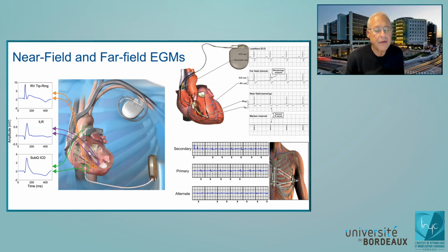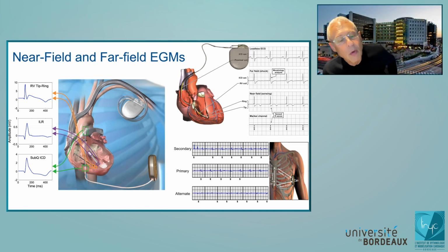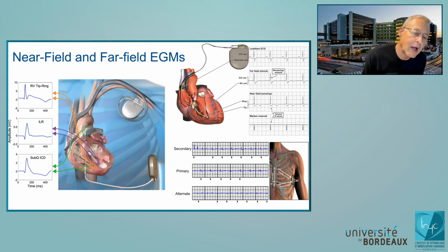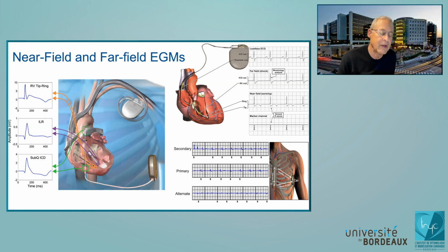The sensing characteristics of the primary sensing vector, which is between two small ring electrodes, so they're not like shock electrodes, they're more like the sensing electrodes in SICD, but they're smaller and closer together, is that it's somewhat intermediate between SICD, between subcutaneous and intracardiac. It's bigger than a subcutaneous, but typically unfiltered electrograms are 3 or 4 millivolts. However, I will spend a minute on the concepts here, and then I can show you pictures if we get to the end, if you have any interest.